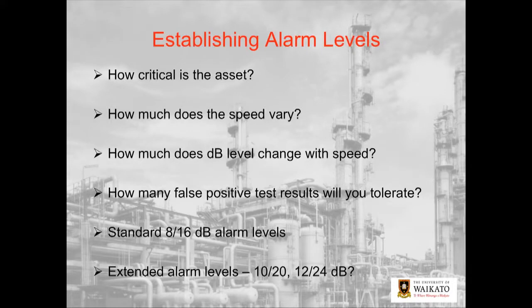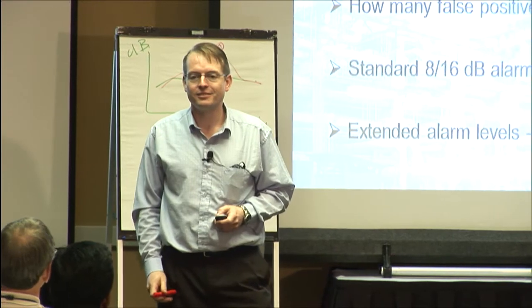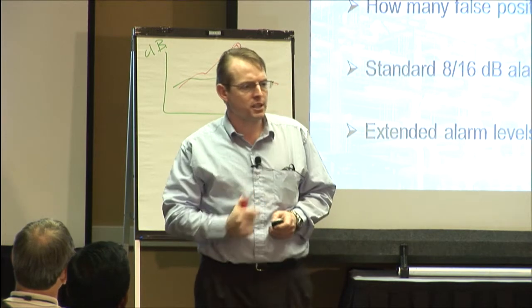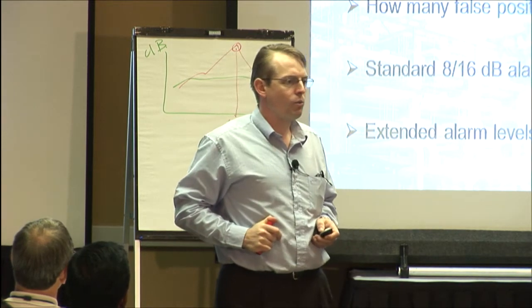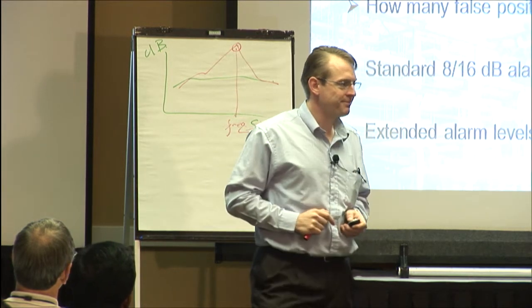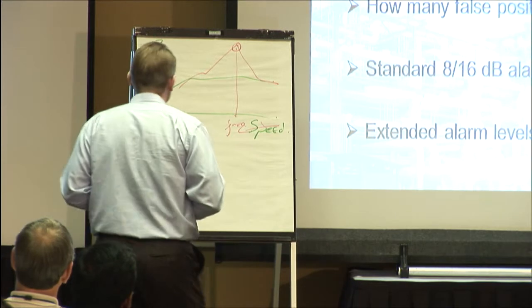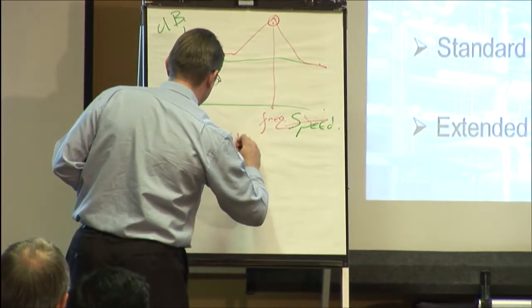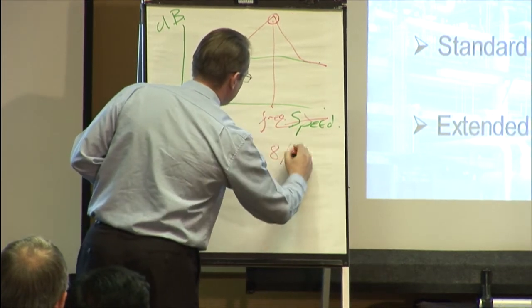All right, so establishing our alarm levels. First question. How critical is my piece of equipment? Why is that number one? It's your money maker? Yeah, okay, I'll accept that. Okay, so we decide that something's critical. What's that going to do to how we set the alarm level? Okay, what's our default alarm level? Eight and 16 dB, right?